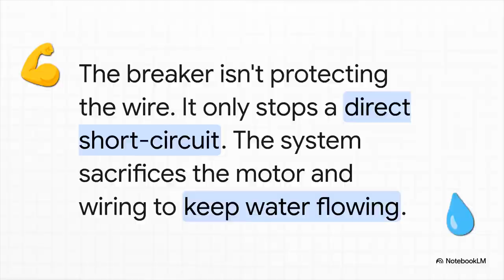And that's the jaw-dropping truth of it. The breaker isn't protecting the wire. Not from overload anyway. It will literally sit back and let that wire glow cherry red, melt its own insulation off, and completely destroy itself, just as long as it means the pump keeps pushing water. The breaker's only job is to stop a direct short circuit, which is an even bigger, more immediate threat. The whole system is designed to sacrifice everything for just a few more precious minutes.